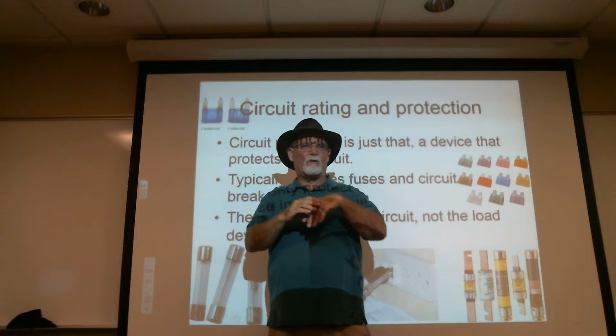The truth is, fuses do occasionally just go. A fuse that's operated at 80 or 90% of its capacity regularly will wear out, will eventually age and eventually go. They can be remarkably difficult to see that they're blown. The really super fine wire ones, same thing here. Kind of from the side, it's fairly easy to see that it's blown, but from the end, sitting down in a holder, it actually can be very difficult to see that they're blown.